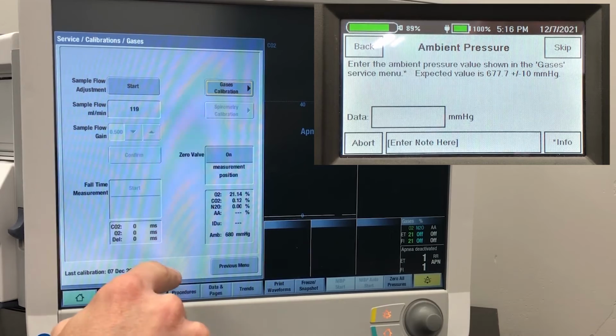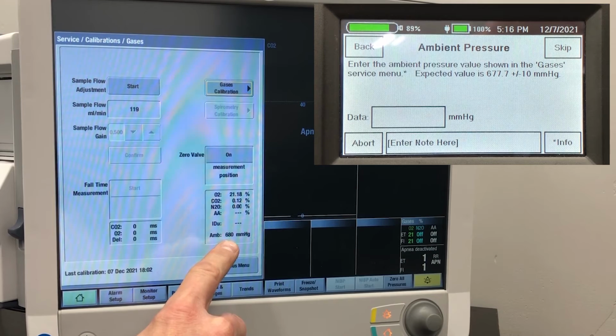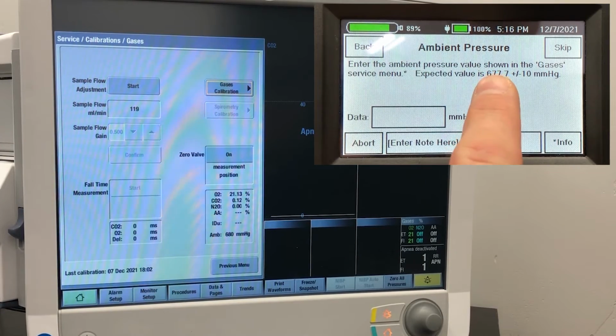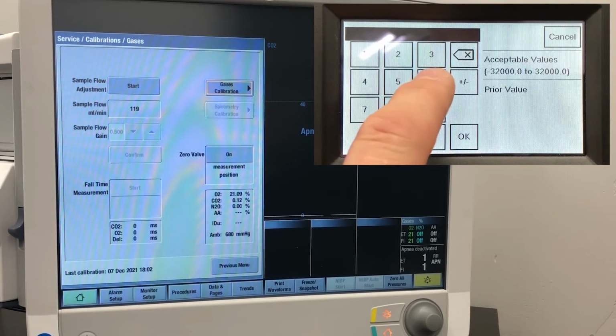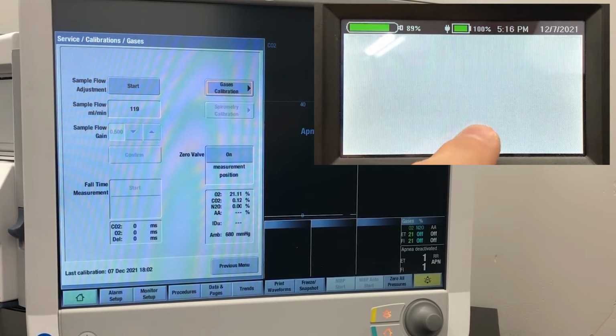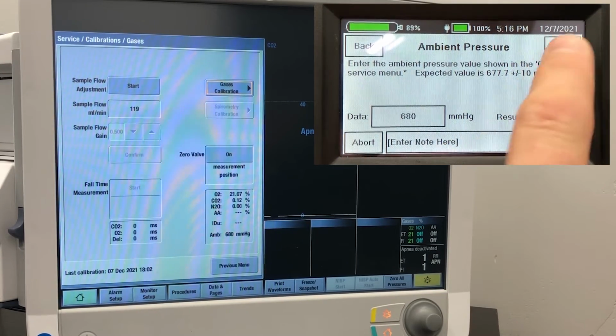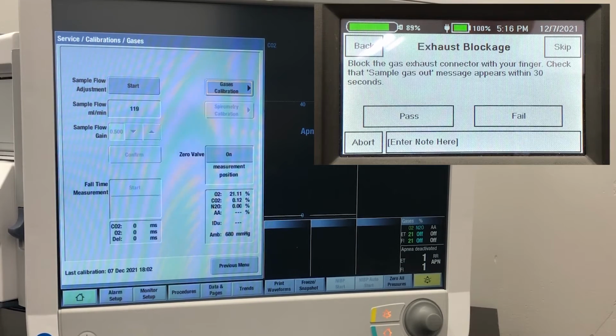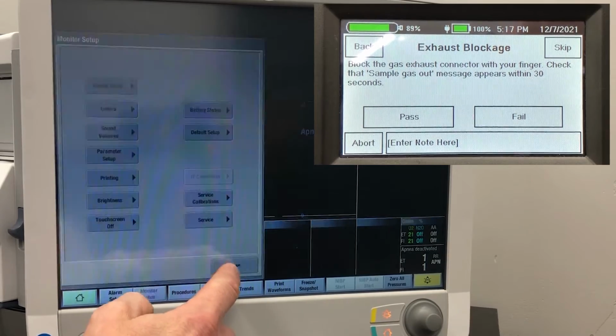We exit out of this menu, which brings us back to the main gas service menu. So this AMB or ambient value gives the ambient or barometric pressure as measured by the gas module, 680 millimeters mercury. The SmartTank's internal NIST traceable barometer measures the pressure as 677, almost 678. So they're reading very close. It's well within the pass criteria, so it's a passing result. Next, we'll test the sample gas out blockage alert. We can exit out of this menu.